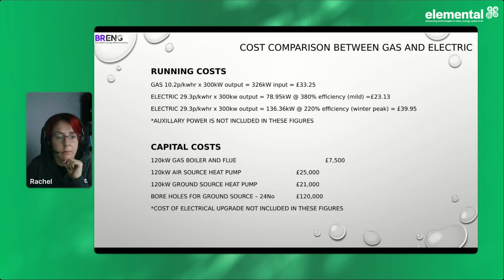But if we compare the capital costs, this is also important for a school. The initial outlay for a 120 kilowatt boiler is £7,500. If you compare that to an air to water heat pump, which is 25, a ground source, which is 21, but then you have to add boreholes for the source on it, usually boreholes, that adds another 120,000. So we've got to look at what is the cost of going carbon neutral and how do we achieve it using the best economies of the equipment we choose.